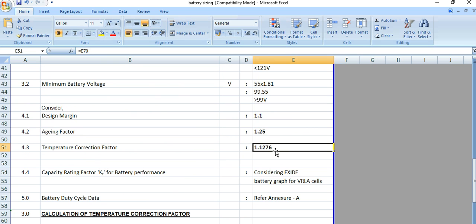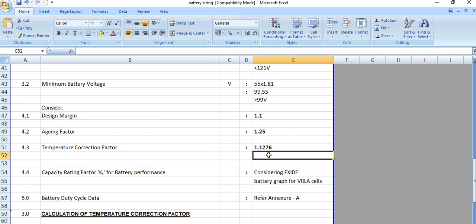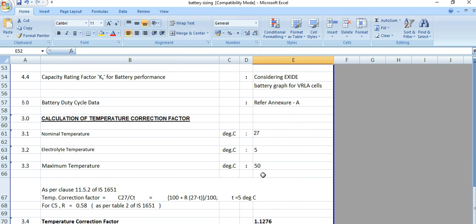There are three key factors to consider in the sizing calculation: the aging factor of 1.25 (25%), the temperature correction factor of 1.1276, and the capacity rating factor Kt. In the next video, I will cover the battery duty cycle.